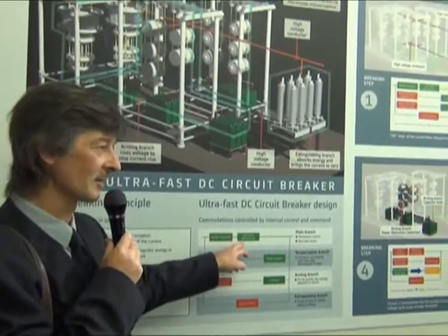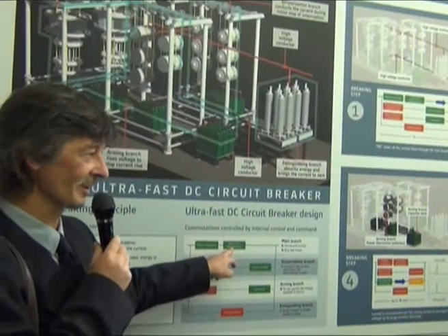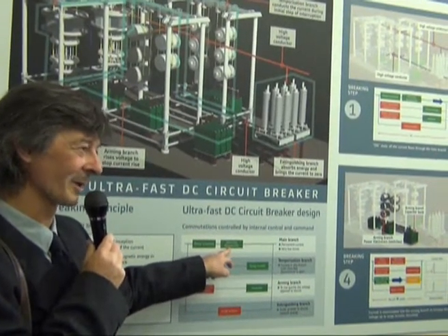And I'm saying it's not very fast, but it's a question of hundreds of microseconds. So not very fast, but quite fast anyway. Completely electric. There is nothing with spring with it. We minimize the mass in the whole system. This is why the whole system, actually the drive and the linkage in between, has completely been redesigned. Just because you have to be fast, you have to lose mass.